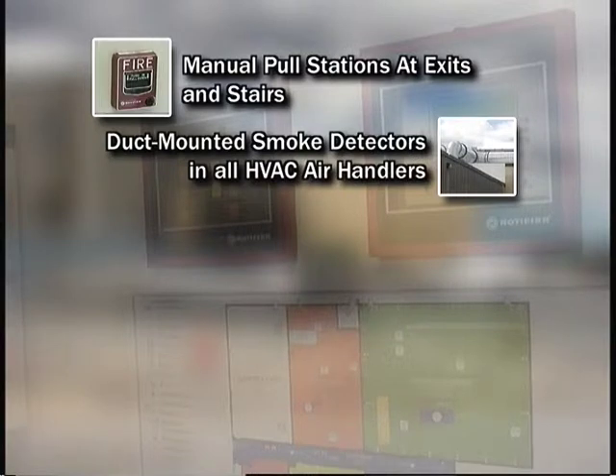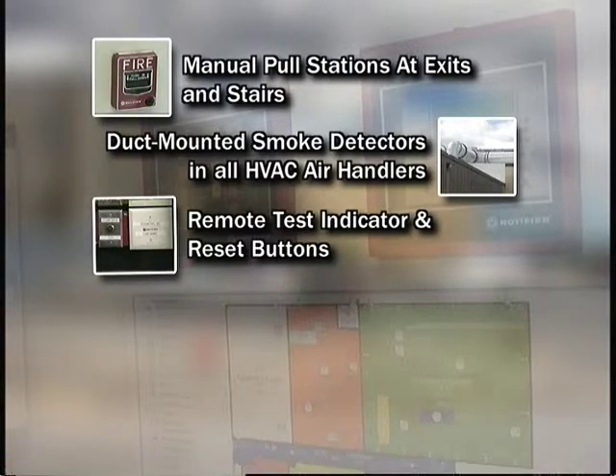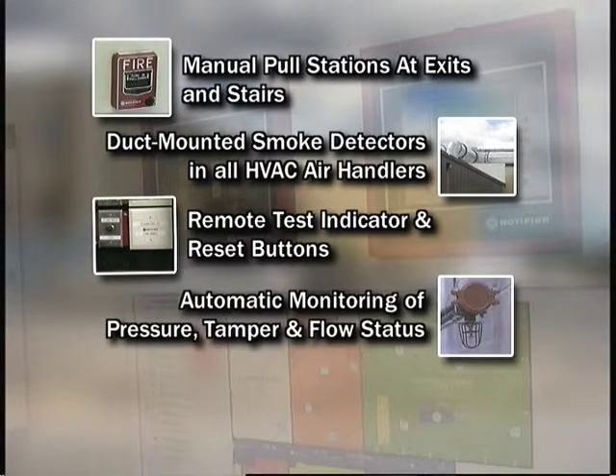Mechanical system monitoring includes duct-mounted smoke detectors to monitor supply-side ductwork of all HVAC handlers moving more than 2,000 cubic feet per minute. The duct smoke detectors are provided with remote test indicator and reset buttons. These are located in corridor areas outside the space served by the associated unit and prominently identified. The main sprinkler system and riser valves are provided with automatic monitoring of pressure, tamper, and flow status at the zone valve assembly.